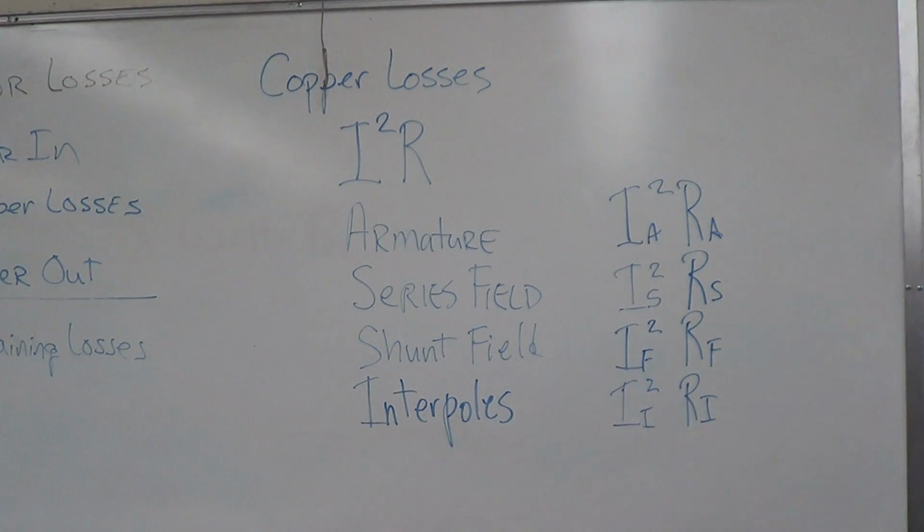Do they tell you an efficiency rating on its nameplate? Not an efficiency. You can calculate what the efficiency is. You can calculate nameplate power in. You've got power in, you've got power out, so you can calculate the efficiency. When you purchase a motor, there may be super E, super efficient, with efficiency ratings, but in this case, there's no efficiency stamped on it.